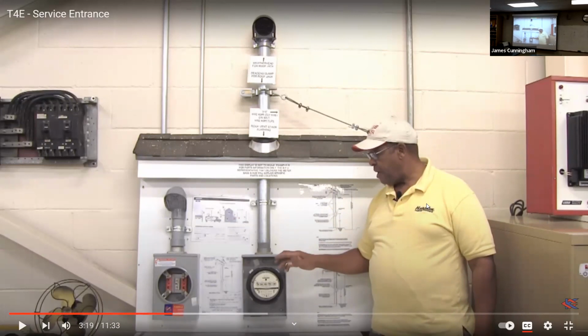You have a meter main, so the electrical comes into the box, a separate box where the meter is located. And then from the meter, it goes through a conduit that Edison controls, and then it comes into your service panel. Most of the time now, what you're seeing is that the electrical panels have what they call a meter main. So both the meter and the circuit breakers are all together in one panel. So the panels are much bigger now. And so you have to create a bigger space in the wall for those.